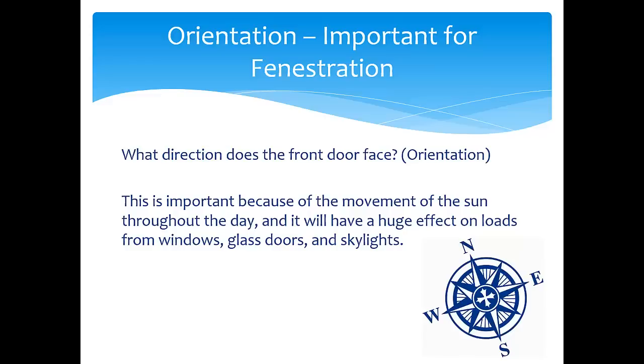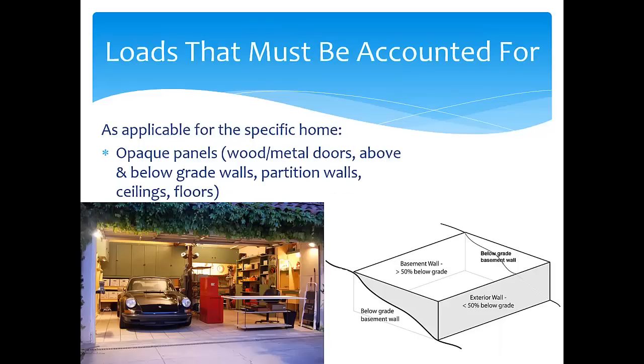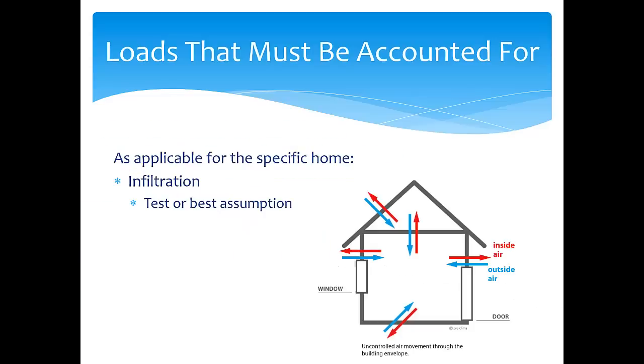The next set of loads that a designer has to account for are the opaque panels. These include wood and metal doors, above and below grade walls, exterior walls, partition walls, ceilings, and floors. The designer needs to account for each one of these. Infiltration is the next load — it's the uncontrolled air leakage into the conditioned space: the cracks, the openings, and also leakage through the attic, the ceiling, crawl spaces, and/or the basement if applicable. The most precise way to get the infiltration load is to measure it directly using a blower door. But if the home's not built yet, Manual J has some default values that can be used based on construction assumptions.